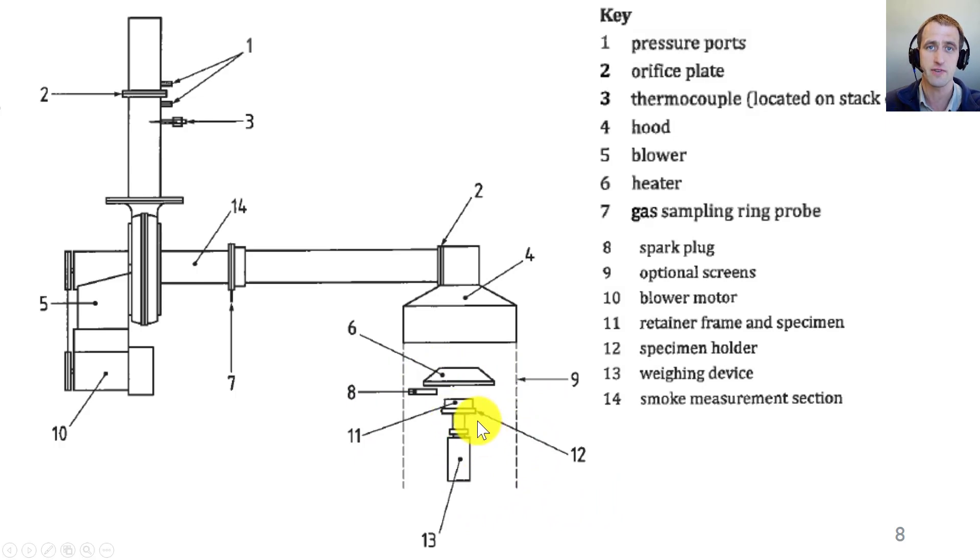This is the simple sketch of the setup. The main thing is you have a sample on a scale and we will measure the mass loss of that with time. But then also we have a cone that emits a flux onto our sample. The gases go up the cone into a hood, down a pipe, and then get forced out. There's forced extraction, there's a fan, and so we will measure the oxygen concentration with time. We can also measure other things—H2O, CO2, and CO—but the main thing is the oxygen concentration with time.